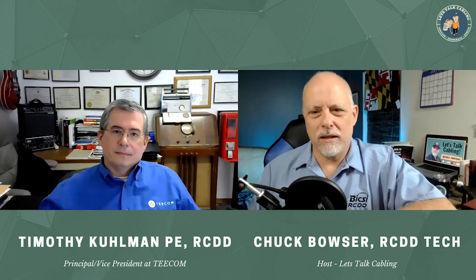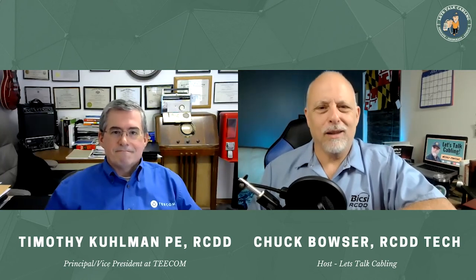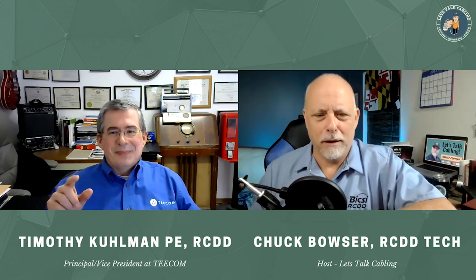Okay, very good. Every time I talk to you, Tim, I learn something new. Actually, I learned more than one thing today. The takeaway I got from today's show is, if it meets the six requirements of an information technology equipment room, and it's a plenum rated raised floor, you can put riser rated cable in that environment. But you can't do it if it's in the ceiling and it's a plenum rated ceiling. But here's the key: you may not want to.